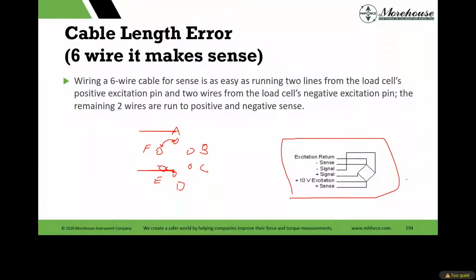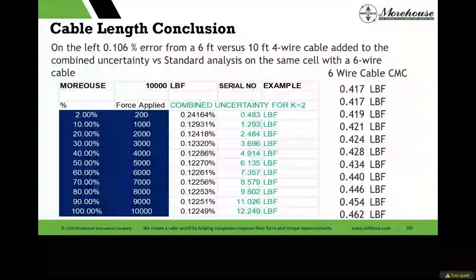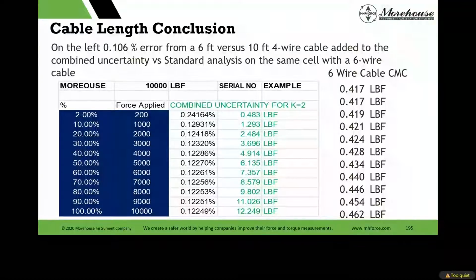So the signal lines B and C just run to whatever connector you need to run to, and then you double up your excitation. You put two wires on A and two wires on D. So A would get positive, D would get negative excitation, and your negative sense line would be run on the same line. Absolutely no problem to do this. It will work. It's very easy. Why in the world would I not use 6-wire? Like I said, you like your indicator for some reason.